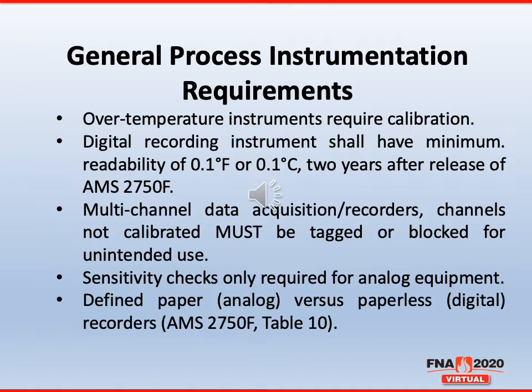One good thing is that sensitivity checks for digital instrumentation are no longer required. The sensitivity checks are only going to be required for analog equipment. And we also put in a new table, Table 10, which defines what is an analog instrument and what is a digital recorder. So we have the paper versus paperless recorders spelled out in Table 10 of AMS 2750F.